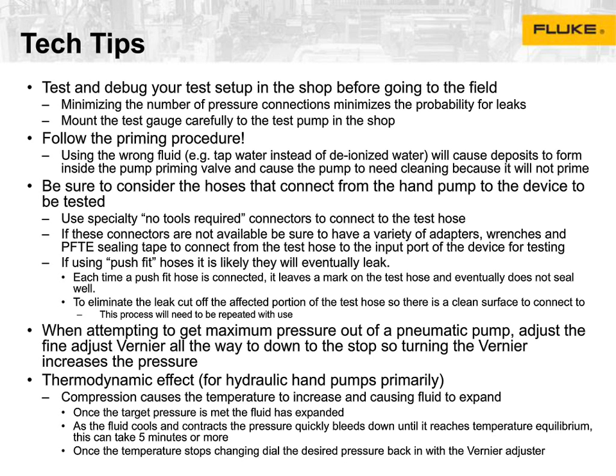One thing that we see a lot of new guys do is they don't adjust their vernier prior to actually pumping up to pressure. So make sure you take your vernier all the way down, and then as you pump up, stop a little short and use your vernier to ease up to the pressure you need in order to hit your point.